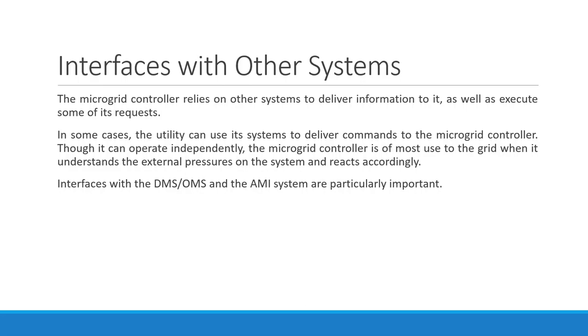In some cases, the utility can use its system to deliver commands to the microgrid controller. Though it can operate independently, the microgrid controller is of most use to the grid when it understands the external pressure on the system and reacts accordingly. What is the information? Basically, your distribution management system, or OMS, or automatic metering infrastructure system, whatever data it is sending, according to that it is going to take the decision. Particularly, maybe there is a fault, so current would be high, so it should be disconnected somewhere. You can think in that way. So interface with other systems, with other entities, is required.